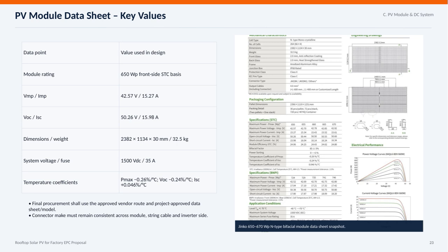Temperature coefficients indicate how performance changes with temperature. We see a reduction in maximum power by 0.26% per degree Celsius, a drop in open circuit voltage of 0.24% per degree, and an increase in short circuit current by 0.046% per degree Celsius. Finally, it's essential that the final procurement follows the approved vendor route using the confirmed data sheet and model. Also, the connector type must remain consistent from the module through the string cable all the way to the inverter to ensure compatibility and reliable operation.